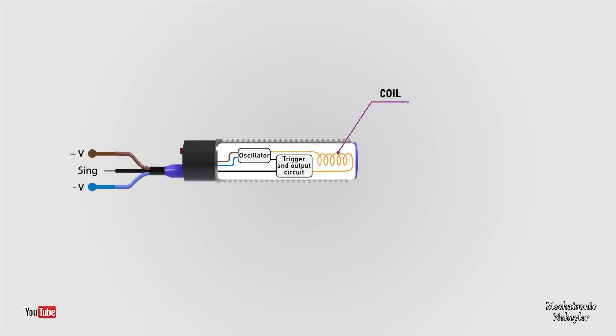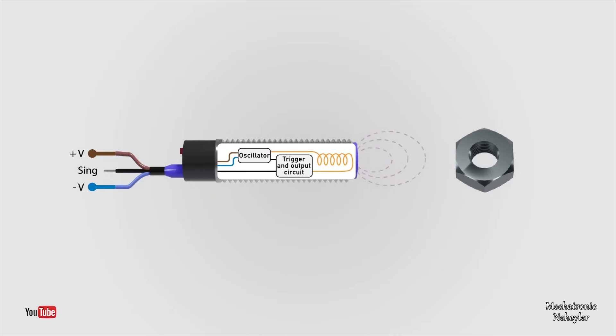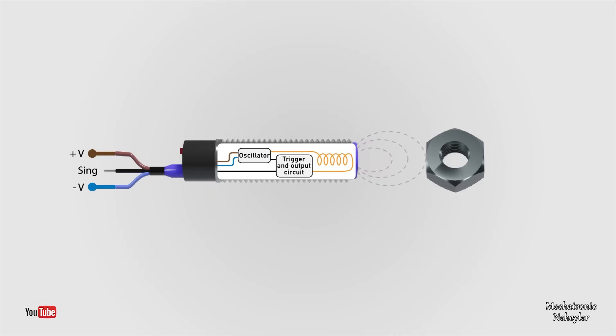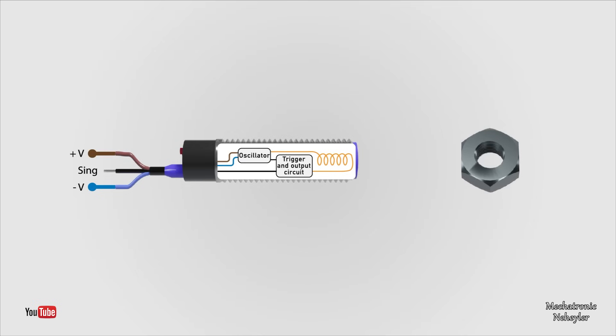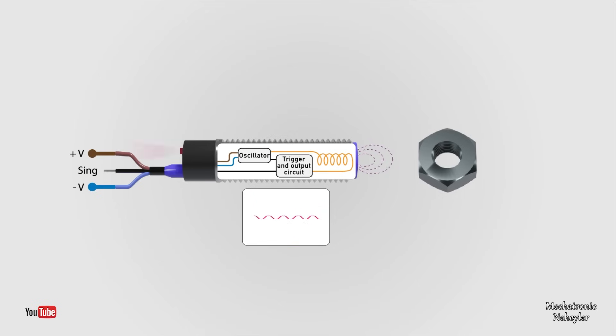The oscillator allows the coil to generate an electromagnetic field. When a metal object enters the electromagnetic field, an induction current, or eddy current, flows in the metal object due to electromagnetic induction. As the object approaches the sensor, the induction current flow increases, causing the load on the oscillation circuit to increase. Then the oscillation fades or stops. The sensor detects this change in oscillation state with the amplitude detection circuit and outputs a detection signal.